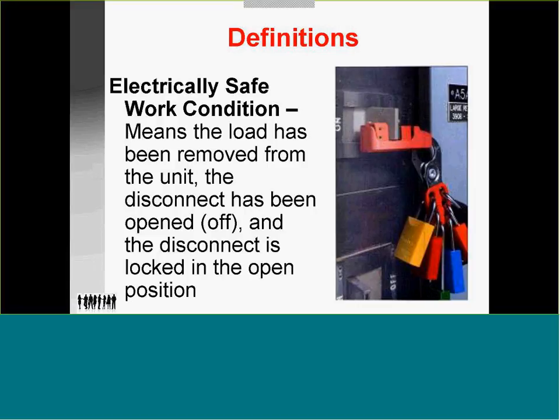Now, this condition means the load has been removed from the unit. It's important to remove the load before disconnecting a breaker, whichever way you want to look at it, because it's not arc rated. It has the potential of creating an arc in the panel. Once the arc begins, the damage increases rapidly due to the heat and can cause significant damage. I have the results of an arc flash on 480 where in less than 1 microsecond, 750,000 amps came into the building, blowing the main electrical room, blew the walls out of it. Never seen force that high before. I've seen it destroy panels, but not destroy the room.